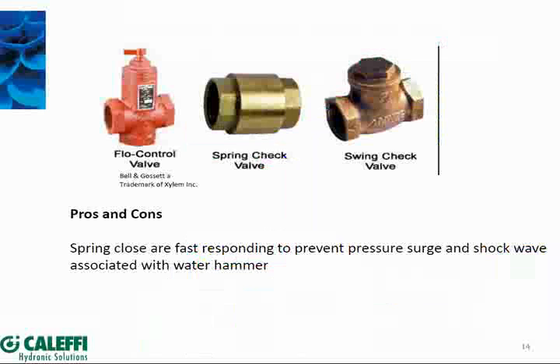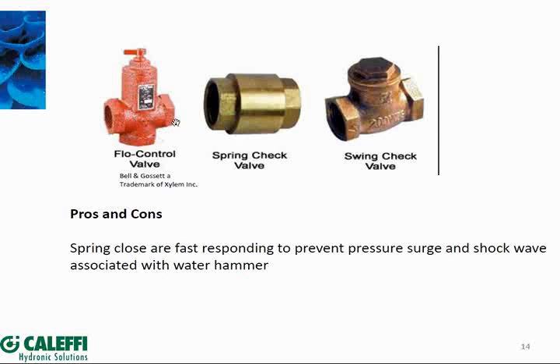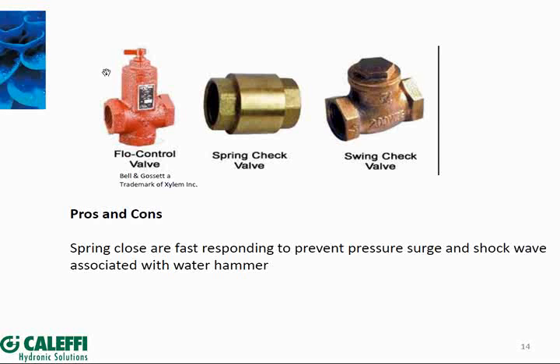Here's what's available in the market to stop flow and prevent thermal migration. The first, courtesy of Bell and Gossett, is a weighted flow check — a weighted plug inside that closes when the pump stops. There's engineering in the shape of that plug so it doesn't vibrate and make noise. It can be used as a straight-through or angle version. For a three-quarter-inch size, it takes about half a pound of lift to open that check valve off its seat and allow flow.